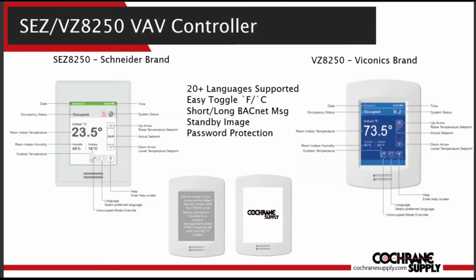8250 supports short and long BACnet messages. The short message, here displayed as room 1705, supports up to a 33-character message that can be anything from a welcome message, which piece of equipment the room controller is connected to, like VAV 237, or even an active value. Maybe you want to display the supply air temperature. This is also the area where alerts are displayed, like window open, dirty filter, or service alarm.